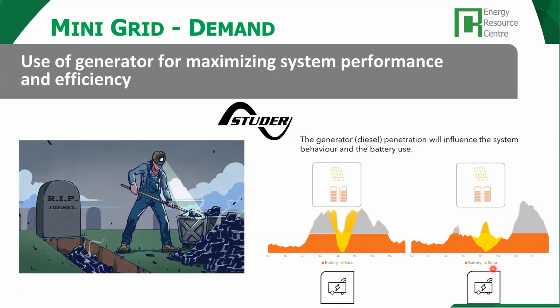Okay, so the diesel genset is always useful. It is useful to build a mini grid, and it's useful to have it as a backup or as a possibility to adapt to changes in the demand without having to worry about the size of the batteries. But what is the problem with the diesel genset? We have a problem of the cost of the diesel, and obviously the problem of the environmental impact of the diesel. So we really want to minimize the use of the genset.